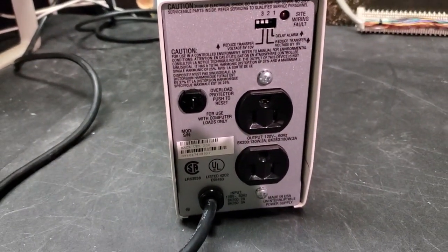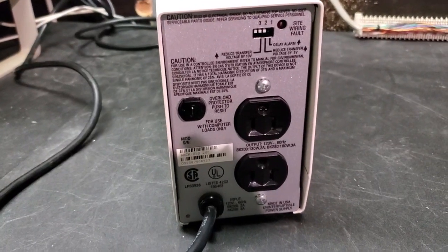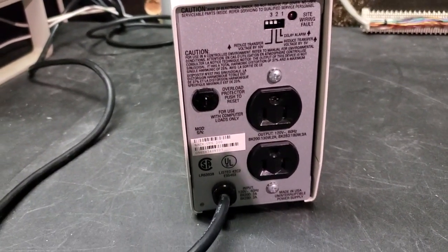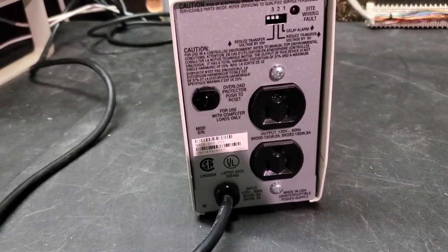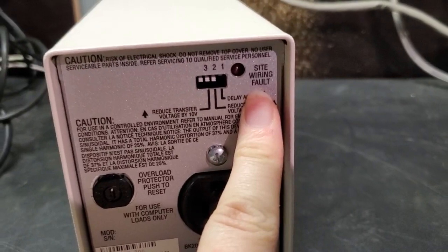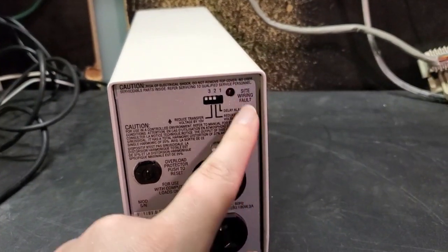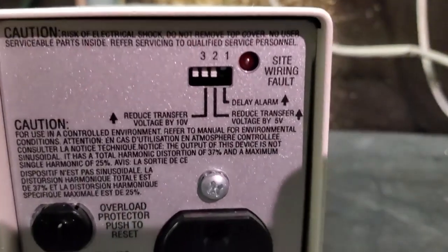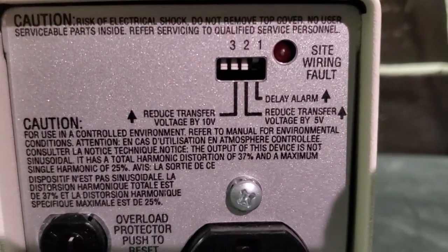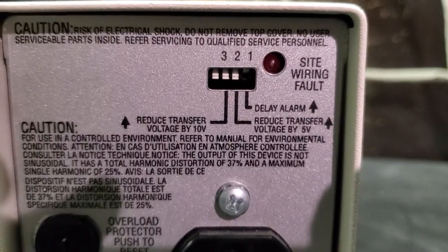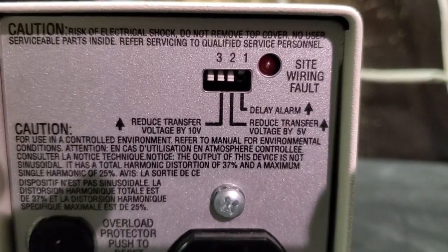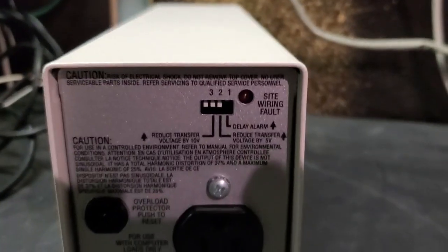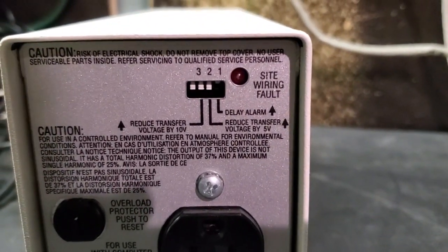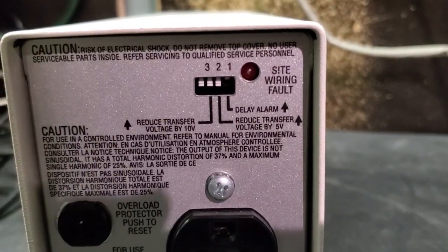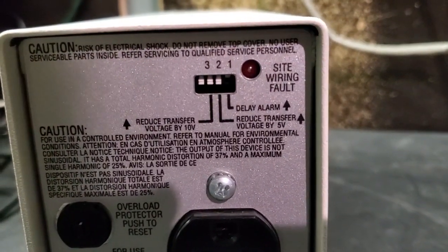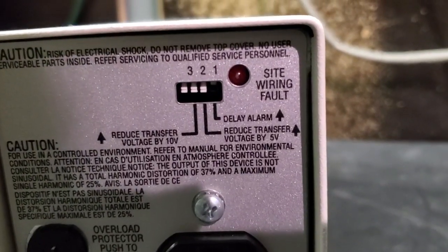The breaker is also rated for 3 amps, which seems a little over capacity to me, but maybe they're accounting for if, you know, you turn something on and there's a bit of a surge. You got a little light to tell you if there's a wiring fault. I assume that means if there's an open ground, that'll light up. And you do get some dip switches here to configure the unit. You've got 2 dip switches here that actually change the voltage at which the UPS will switch to its inverter. So if you want to make it more sensitive, I've got both those switches down so it will be as sensitive as possible. And then you've got a switch to delay the alarm.